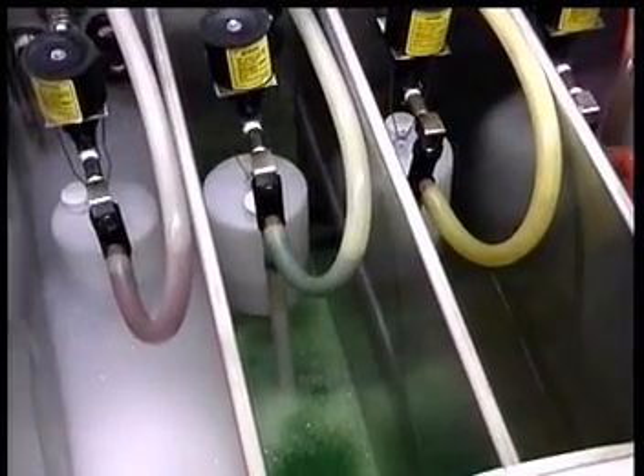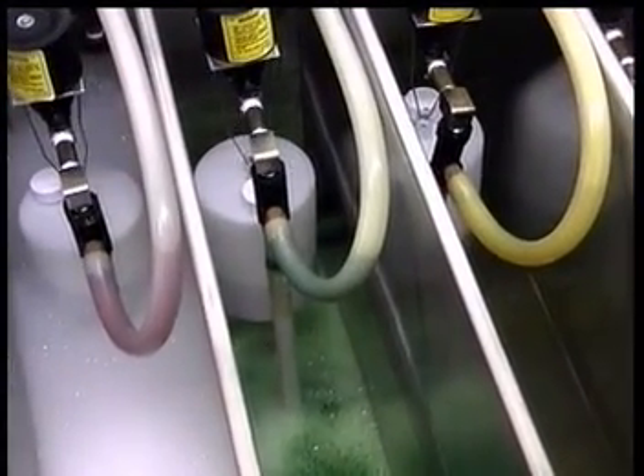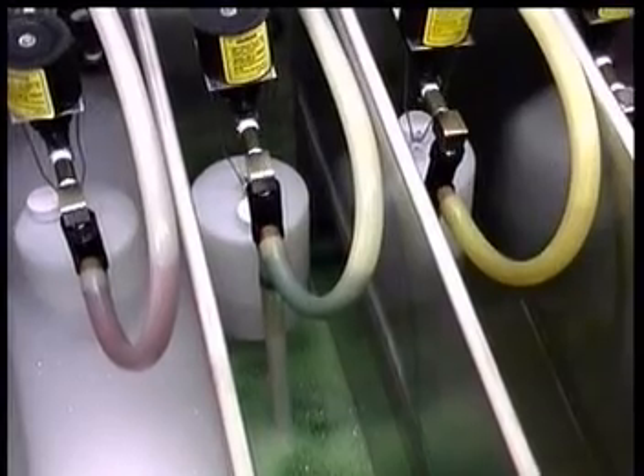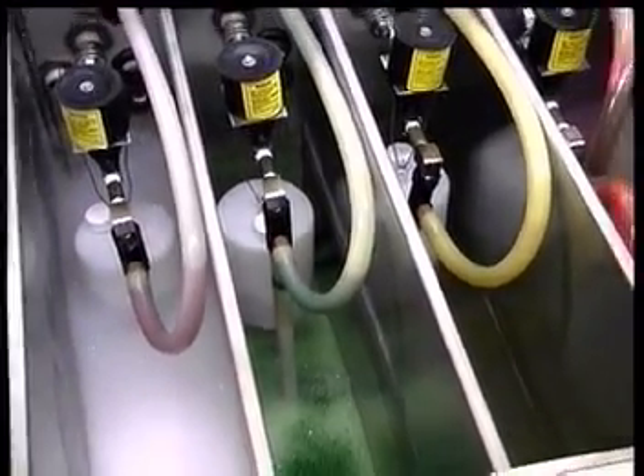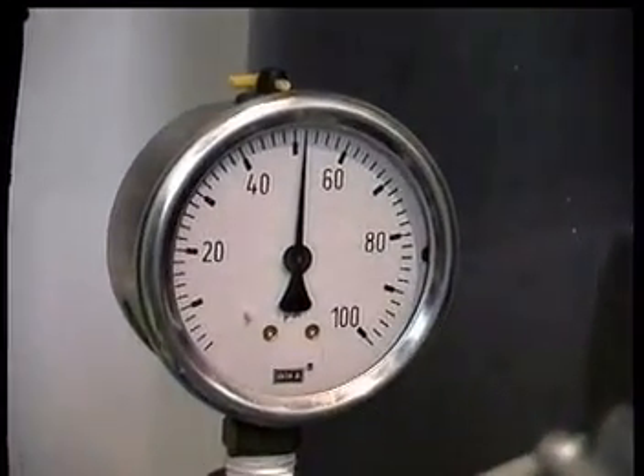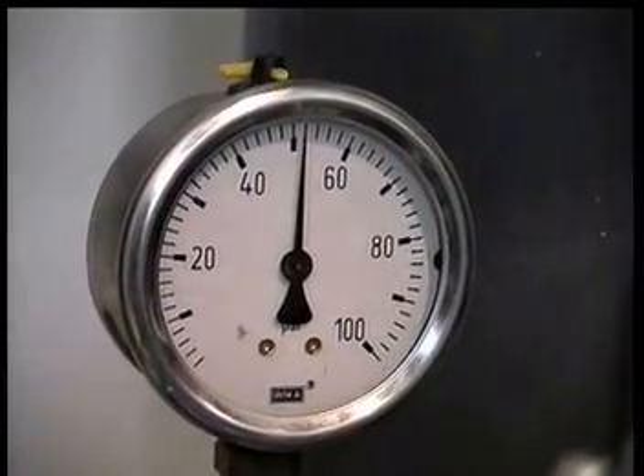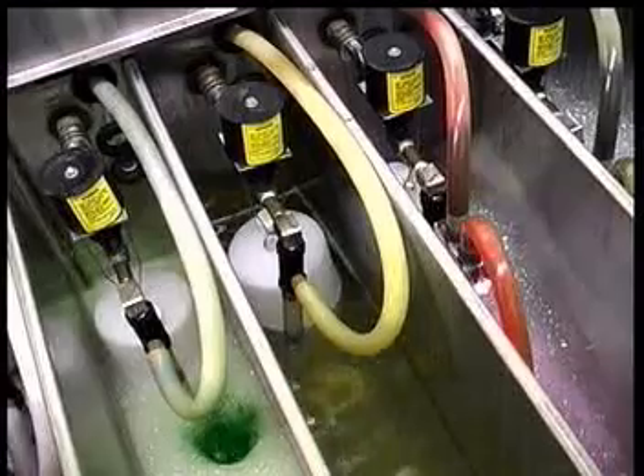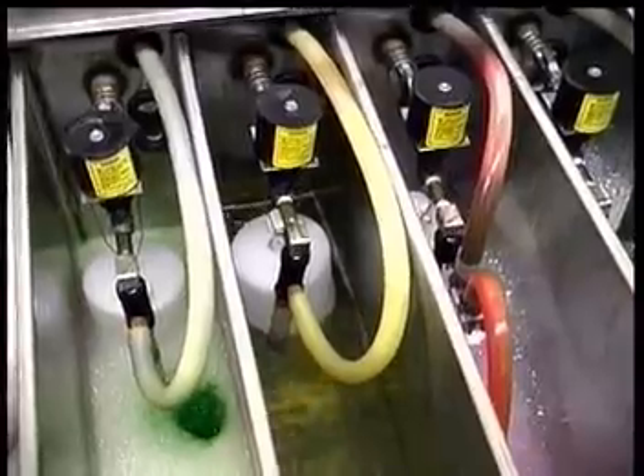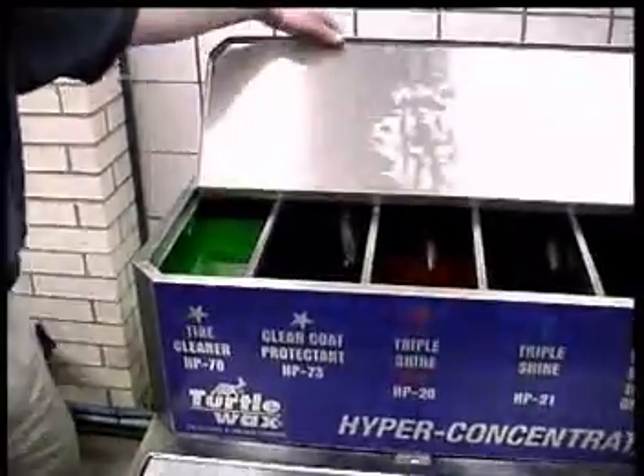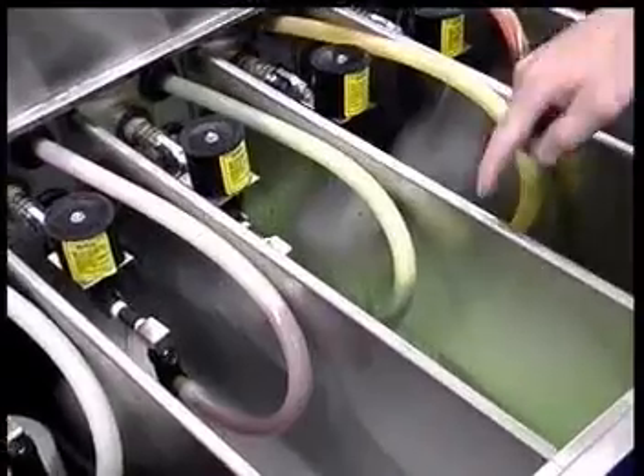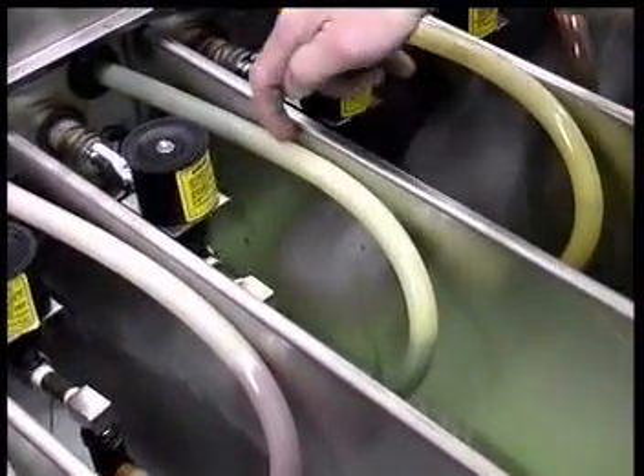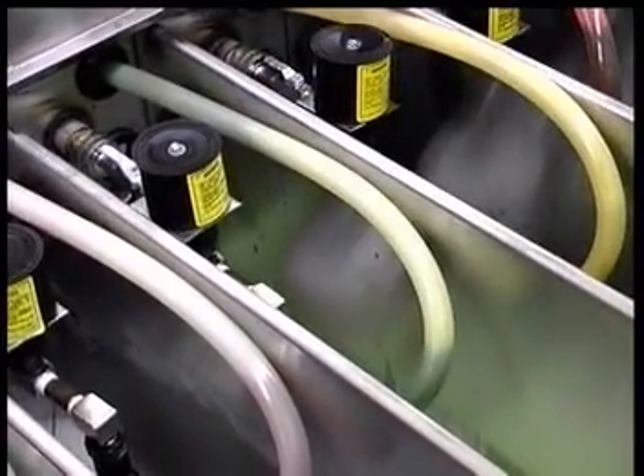If a Hydrominder sticks open, fails to open, or does not mix chemicals as originally set up to do, it requires service. First, verify the water pressure on the inlet is between 40 to 60 psi and the float is not restricted. Then confirm there is chemical in the product tank and siphon hose is full of chemical. A small air pocket at the top of the hose bin is normal.